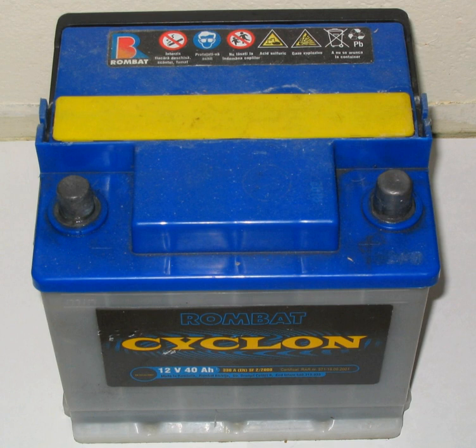If the battery is overfilled with water and electrolyte, thermal expansion can force some of the liquid out of the battery vents onto the top of the battery. This solution can then react with the lead and other metals in the battery connector and cause corrosion. The electrolyte can seep from the plastic-to-lead seal where the battery terminals penetrate the plastic case. Acid fumes that vaporize through the vent caps — often caused by overcharging and insufficient battery box ventilation — can allow sulfuric acid fumes to build up and react with the exposed metals. Ammonia can neutralize spilled battery acid; surplus ammonia and water evaporate, leaving an ammonium sulfate residue. Sodium bicarbonate is also commonly used for this purpose.